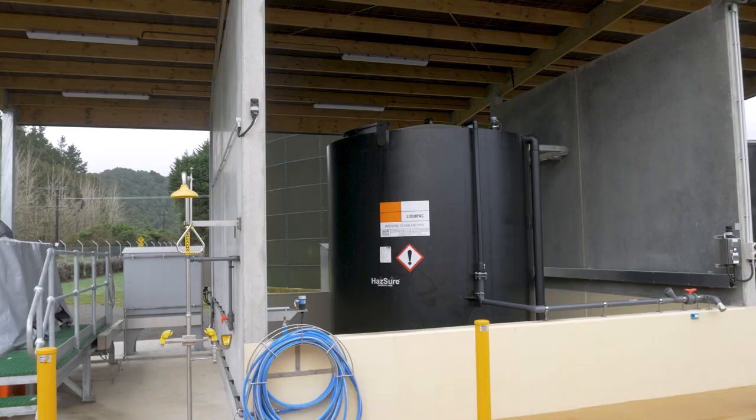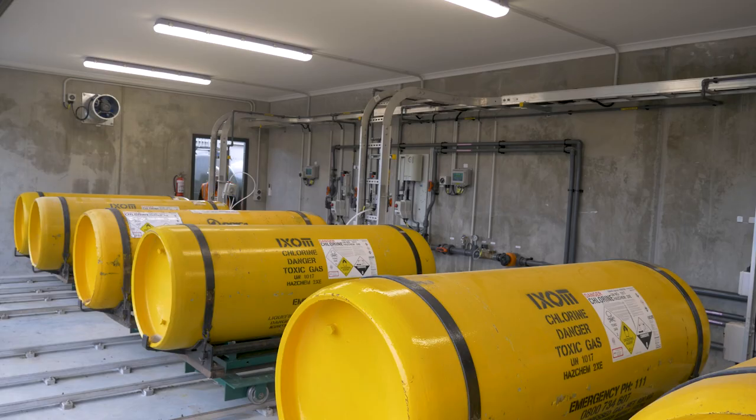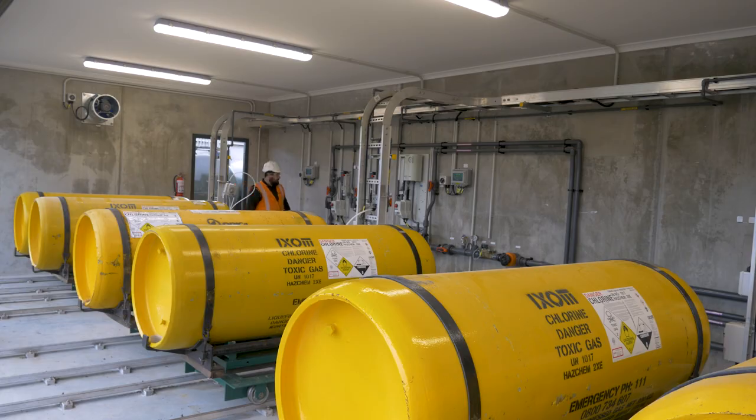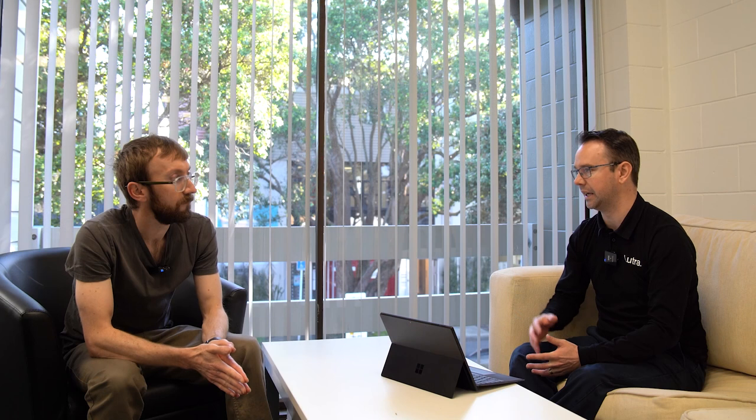Does fluoride dosing affect other processes? Does it affect things like pH or anything like that? Yeah, it does. Within a treatment plant you add many different chemicals for many reasons to make the water safe to drink, and fluoride being typically an acidic effect, it will reduce the pH of the water a little bit, but in most treatment plants they'll be increasing the pH from its natural value anyway to protect concrete pipes and to keep the corrosiveness of the water down. So its effect overall is relatively minor on the water.